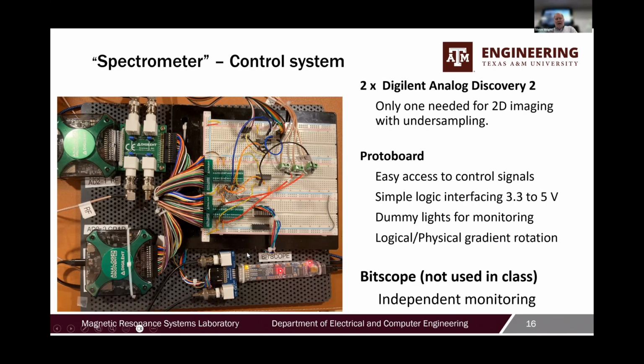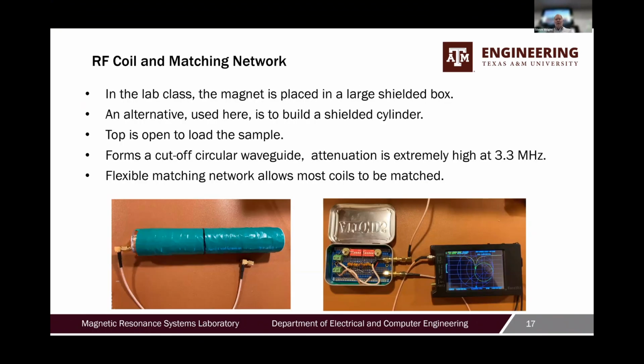This is completely optional. I had that at home and I use it for independent monitoring of the waveforms. So it's not necessary. That's it. The RF coil is a solenoid. It's inside a shield. So the coil sits here. This open shield is a cutoff waveguide, and it gives about 55 dB of attenuation down to the middle of the coil. So it's plenty.